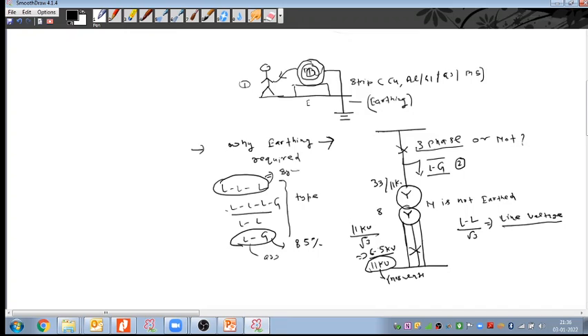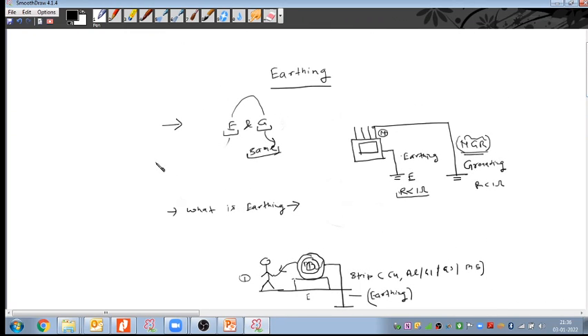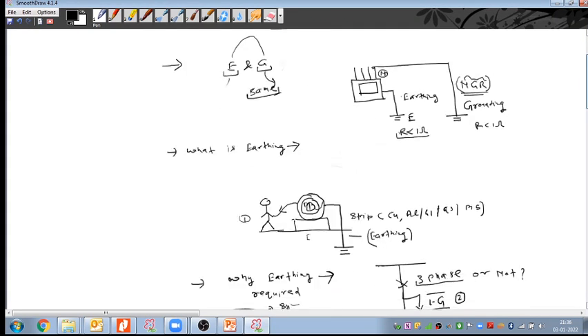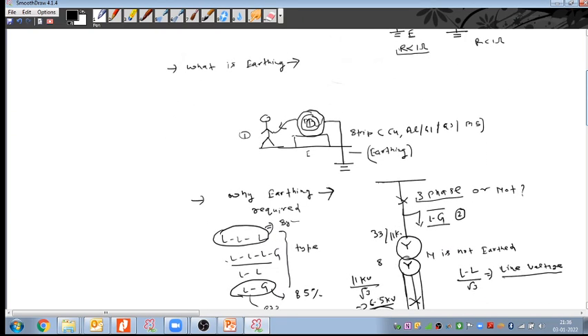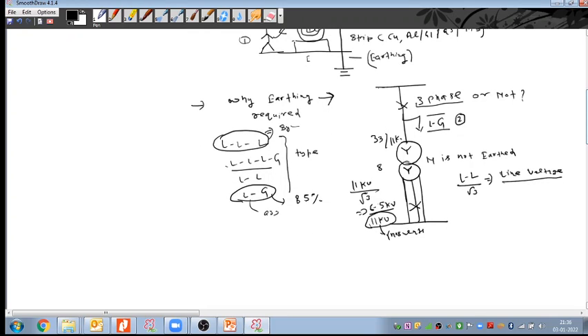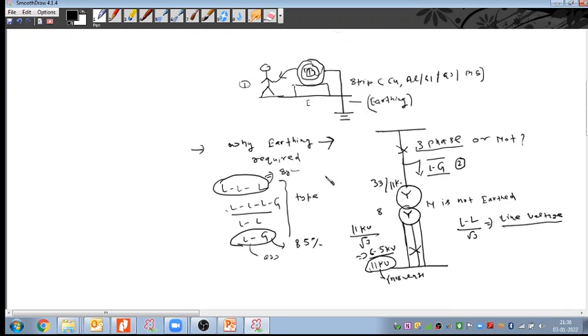So two important points we discussed here. The first: what is the difference between earthing and grounding? The conclusion is that both are the same. The difference is only the convention we used to follow, but technically it is the same. Third, we concluded that if the system is ungrounded, human and equipment are not safe, the line to ground fault cannot be sensed, and the phase voltage will jump to the line voltage.